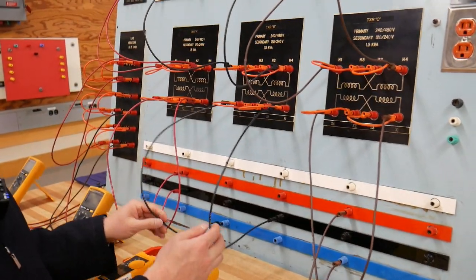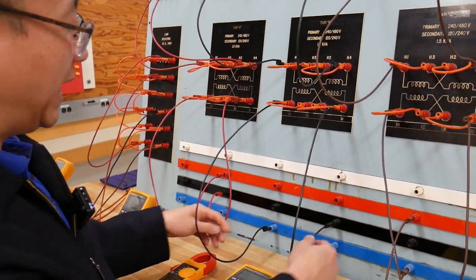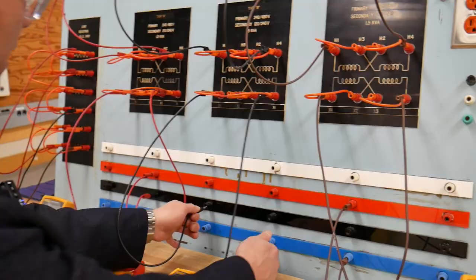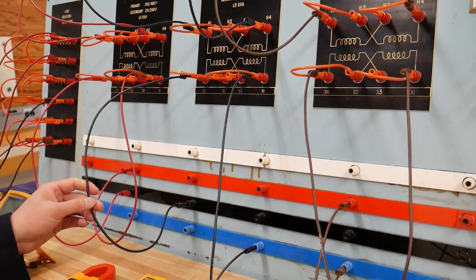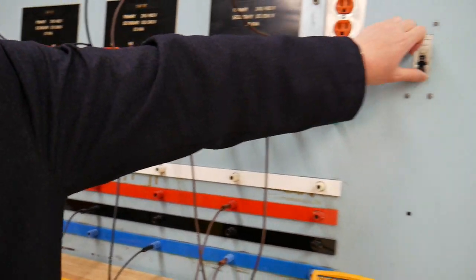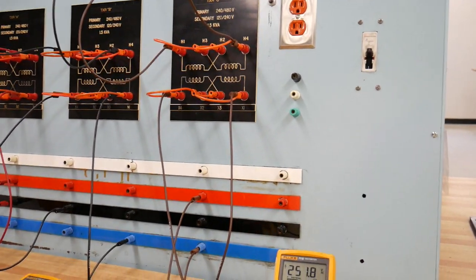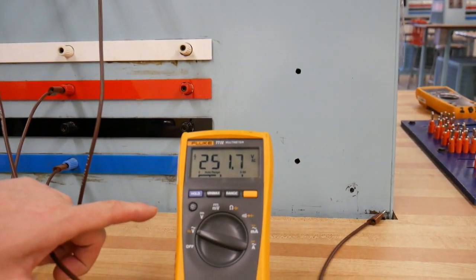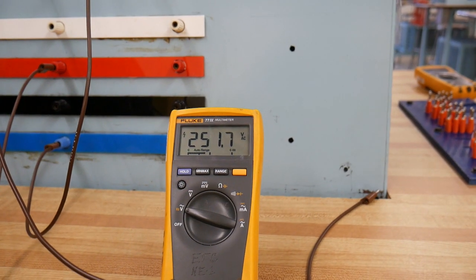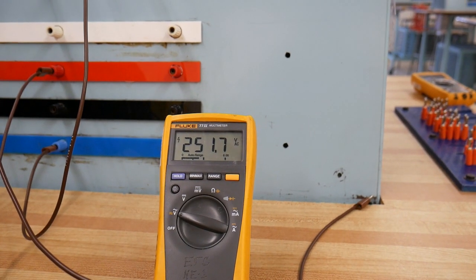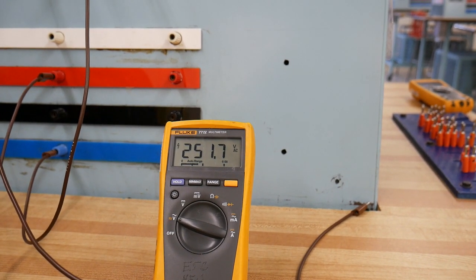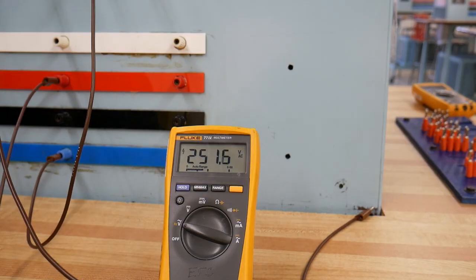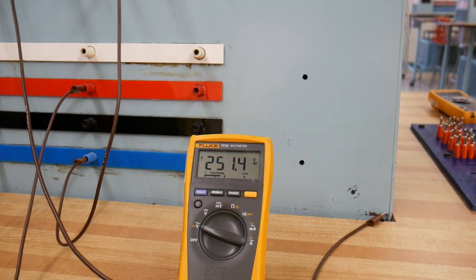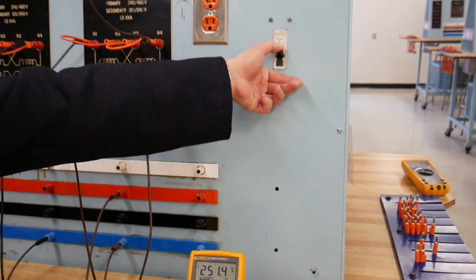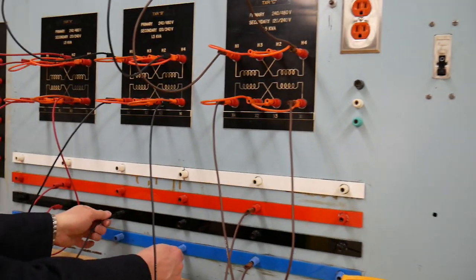Instead of connecting the transformer the right way, I'm going to flip these two jumpers. When I turn the power on, you can see what this voltmeter reads now: 250 volts, double my line voltage. That tells me one of the transformer connections is wrong. So I'm going to flip back to the right connection.